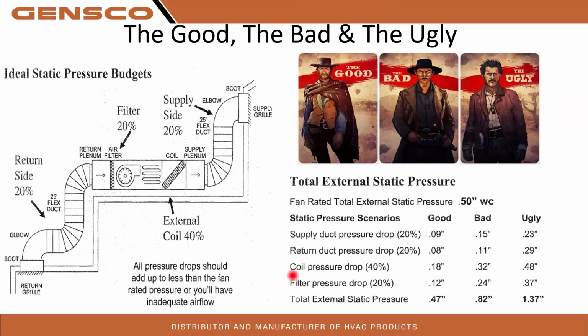This is a great slide that shows you a full system as simple as it can get, right? So we've got our return air grill, a couple elbows, our 25-foot flex duct, and a flex 90 in there, not a hard 90. So we should be 20% of the ideal static pressure for the return side, 20% for the air filter, 20% supply side. Our coil is going to be about 40%. So the good, all right? We see a supply duct pressure drop about 0.09, return duct pressure drop 0.08, coil pressure drop about 0.18, filter pressure drop about 0.12, for a total external static of about 0.47.